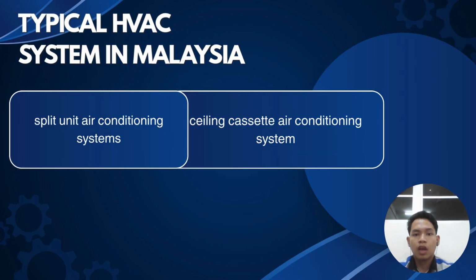occupant load. When looking at the standard market options in Malaysia, the two most widely implemented air conditioning systems are the split unit system and the ceiling cassette system. Wall-mounted split units consist of an indoor evaporator and an outdoor condenser unit connected via refrigerant piping. They feature a lower installation cost and are highly straightforward to clean and maintain, making them highly efficient for smaller, isolated spaces like bedrooms or standard offices. However, they only blow air in a single direction, which can create localized cold and hot spots in large areas.